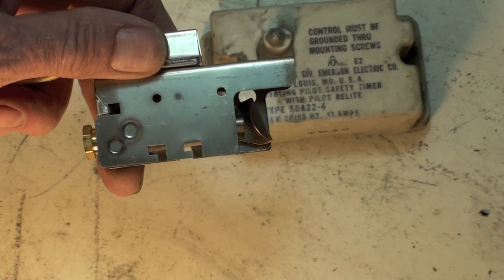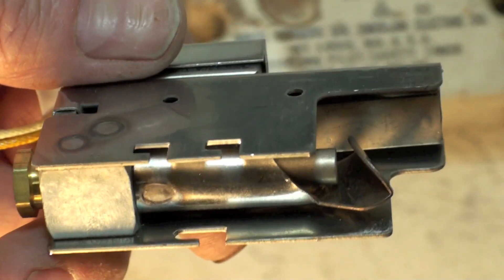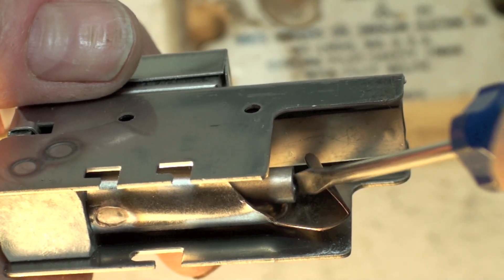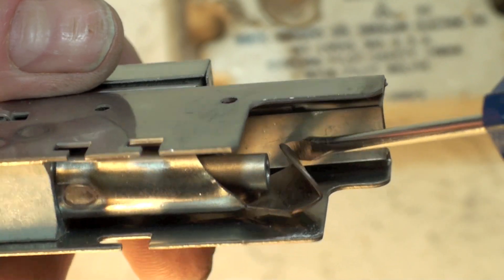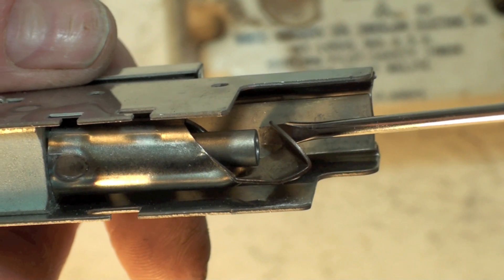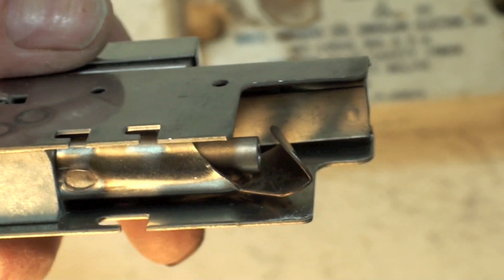Get a little closer and you can see the gas. The pilot gas coming out of here goes up this way to light the burner, goes back here and hits a bimetal. Now that bimetal when it heats up it warps and as it warps it makes a switch.